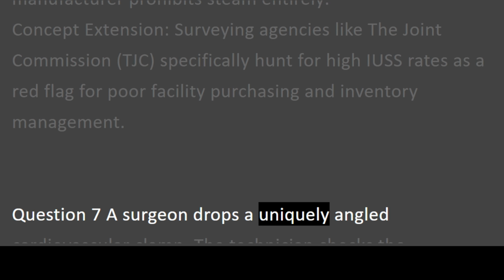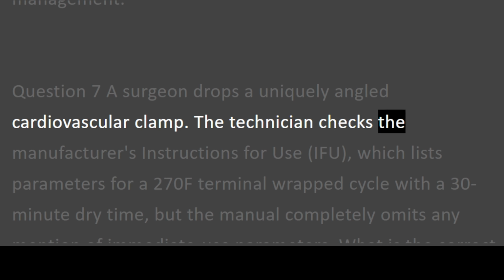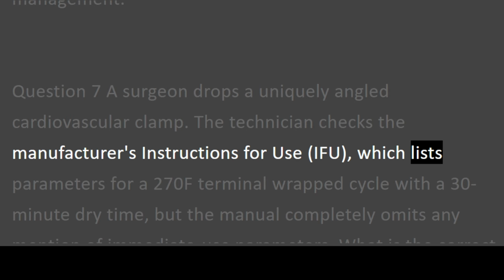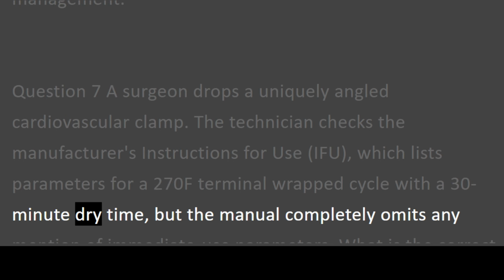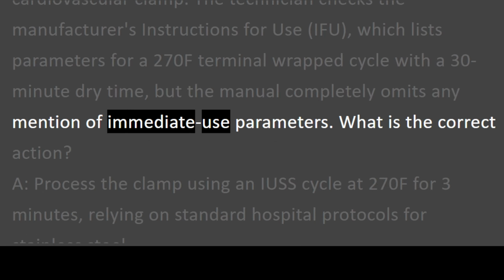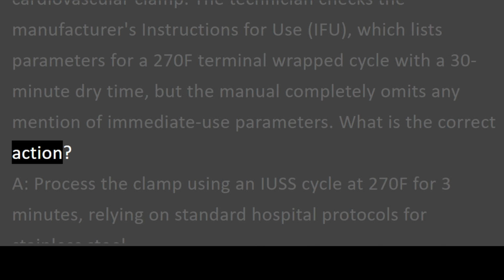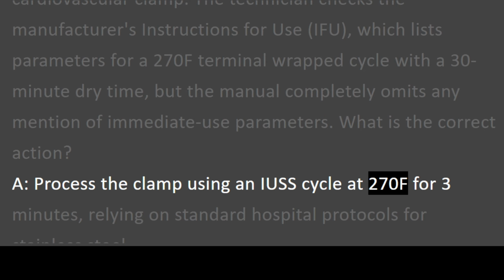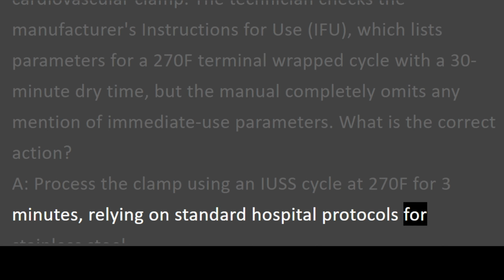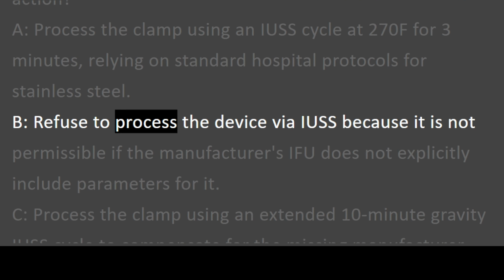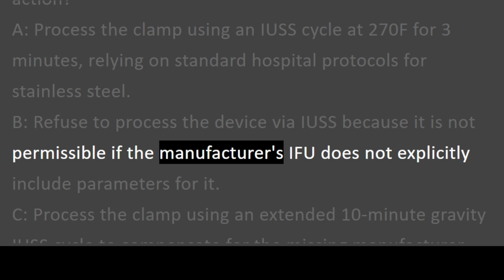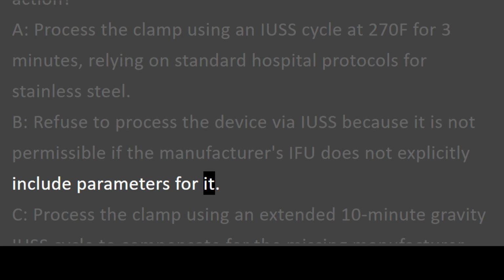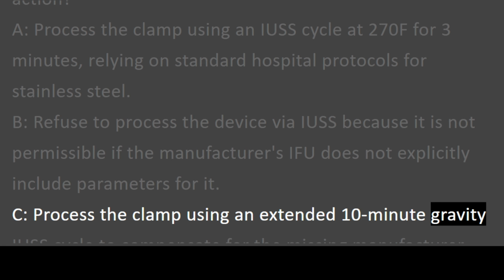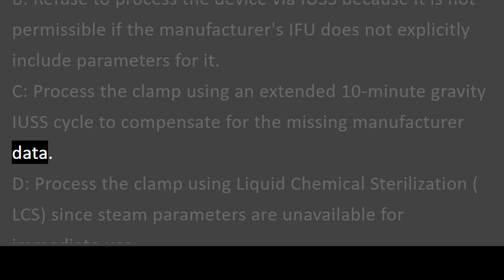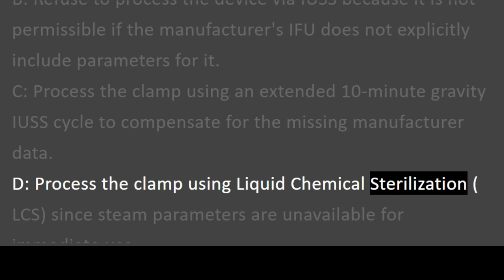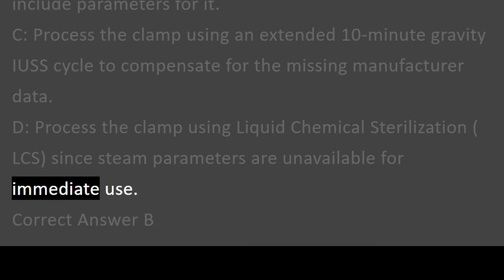Question 7. A surgeon drops a uniquely angled cardiovascular clamp. The technician checks the manufacturer's instructions for use, IFU, which lists parameters for a 270F terminal wrapped cycle with a 30-minute dry time, but the manual completely omits any mention of immediate use parameters. What is the correct action? A. Process the clamp using an IUSS cycle at 270F for 3 minutes, relying on standard hospital protocols for stainless steel. B. Refuse to process the device via IUSS because it is not permissible if the manufacturer's IFU does not explicitly include parameters for it. C. Process the clamp using an extended 10-minute gravity IUSS cycle to compensate for the missing manufacturer data. D. Process the clamp using liquid chemical sterilization, LCS, since steam parameters are unavailable for immediate use.